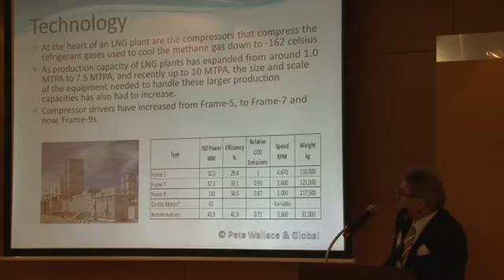We originally used to drive them off steam, as a result of what we normally do in the oil and gas industry. I won't go through all of these. Onshore, we'd use a frame 7 or frame 9 driver, possibly frame 6 depending on the configuration, but these days normally frame 9 if you're looking at a 5 MTPA plant.